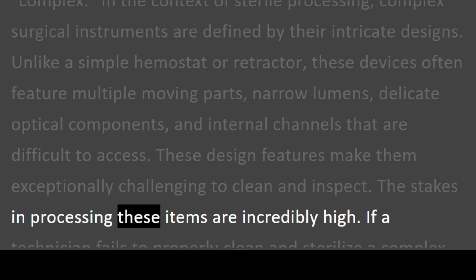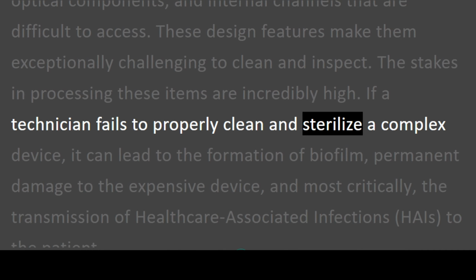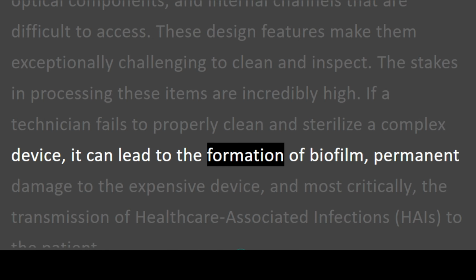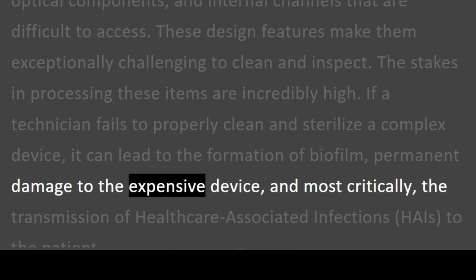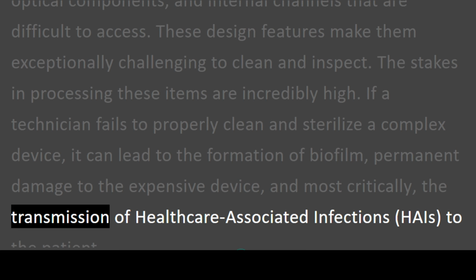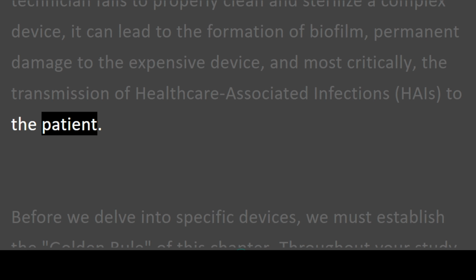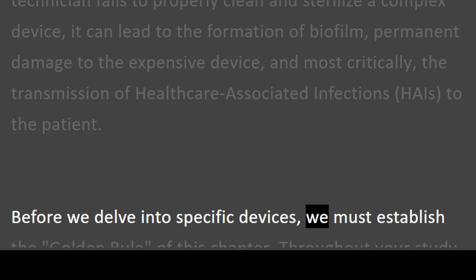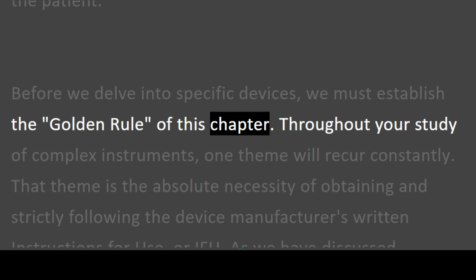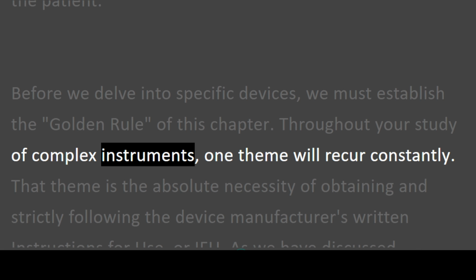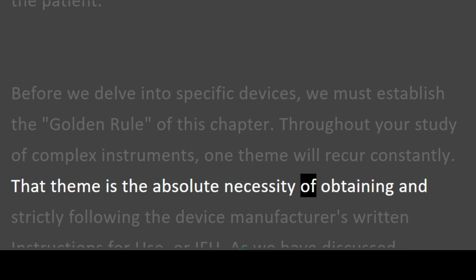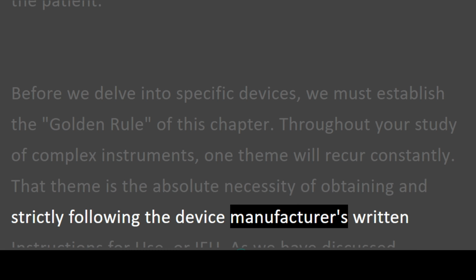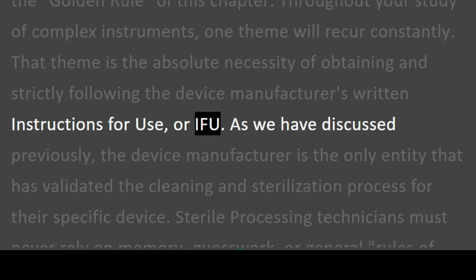The stakes in processing these items are incredibly high. If a technician fails to properly clean and sterilize a complex device, it can lead to the formation of biofilm, permanent damage to the expensive device, and most critically, the transmission of healthcare-associated infections, HAIs, to the patient. Before we delve into specific devices, we must establish the golden rule of this chapter. Throughout your study of complex instruments, one theme will recur constantly. That theme is the absolute necessity of obtaining and strictly following the device manufacturer's written instructions for use, or IFU.